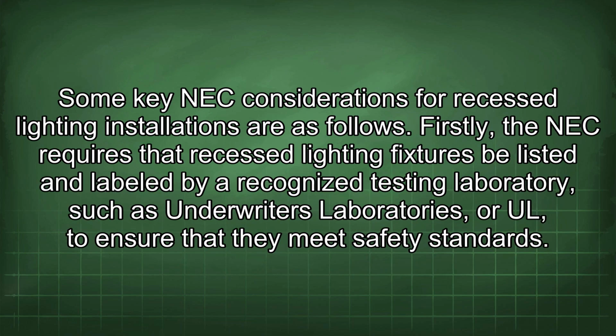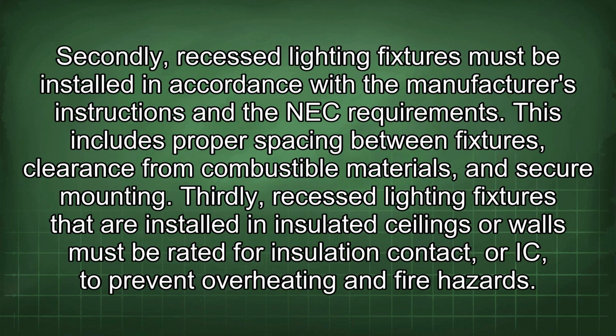Some key NEC considerations for recessed lighting installations are as follows. Firstly, the NEC requires that recessed lighting fixtures be listed and labeled by a recognized testing laboratory such as Underwriters Laboratories, or UL, to ensure that they meet safety standards. Secondly, recessed lighting fixtures must be installed in accordance with the manufacturer's instructions and the NEC requirements. This includes proper spacing between fixtures, clearance from combustible materials, and secure mounting.